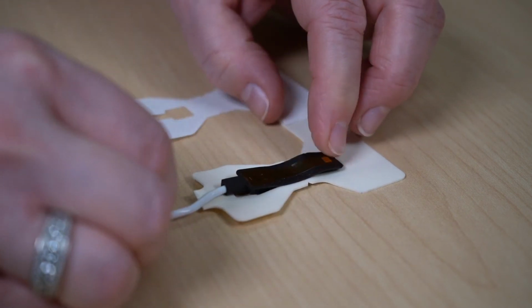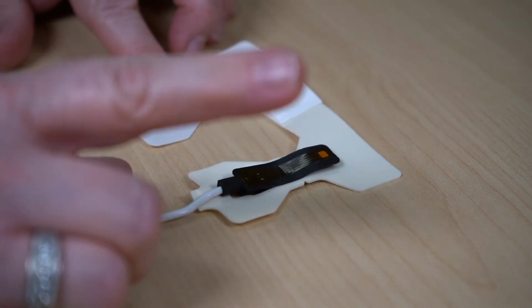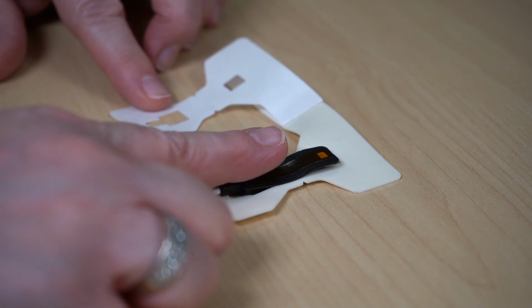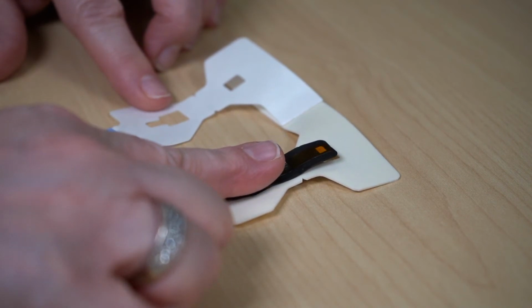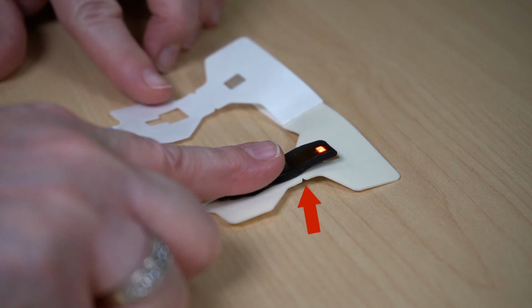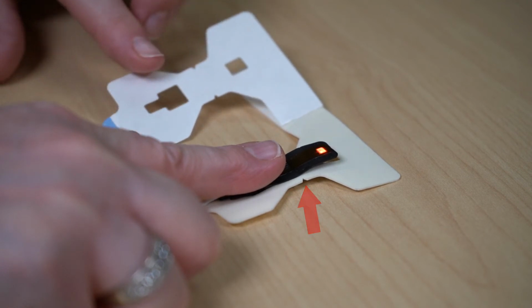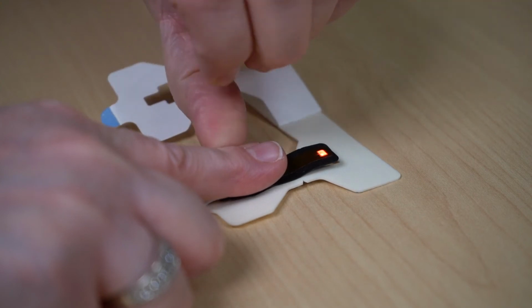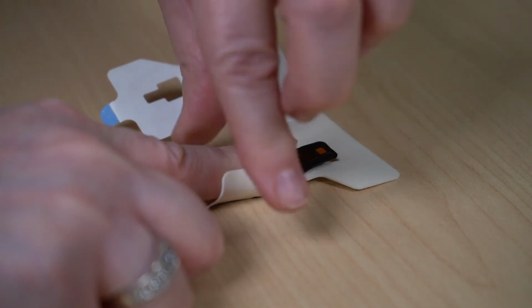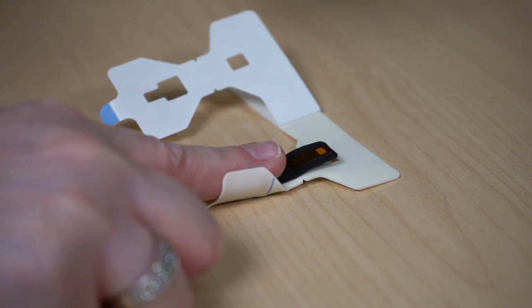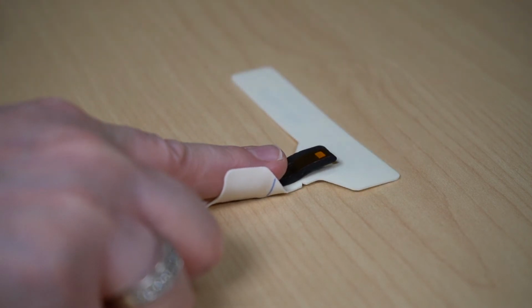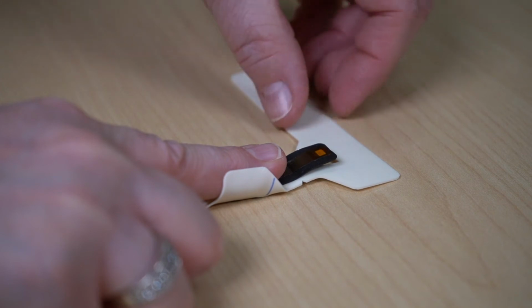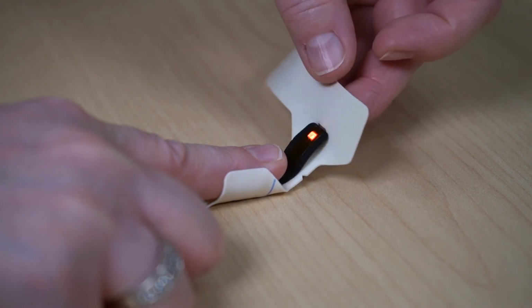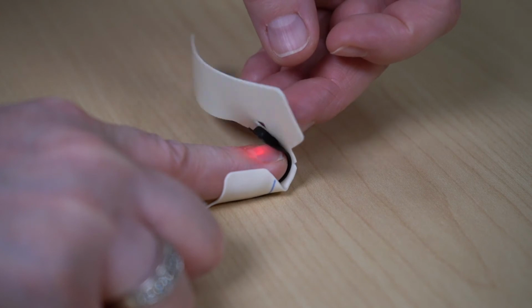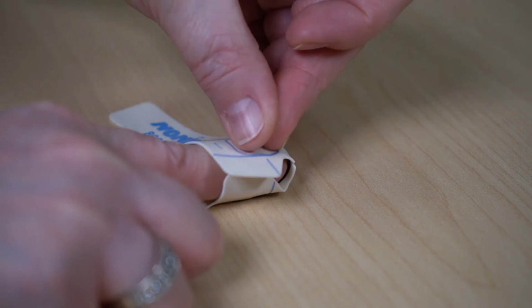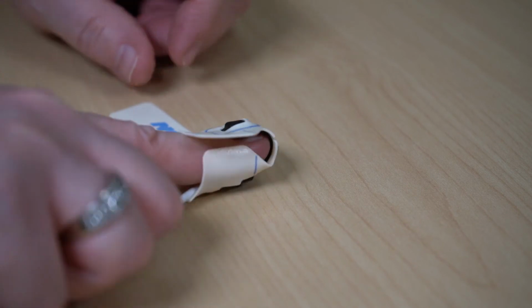on the adhesive. With your fingernail facing upwards, place the tip of your middle or index finger in the center of the probe underneath the notches in the adhesive wrap. Secure the small side tabs of the adhesive on either side of your finger. Remove the rest of the paper backing from the adhesive wrap. Fold the upper part of the probe onto your fingernail. The red light should be on top of your nail bed. Secure the small side tab onto the side of your finger.